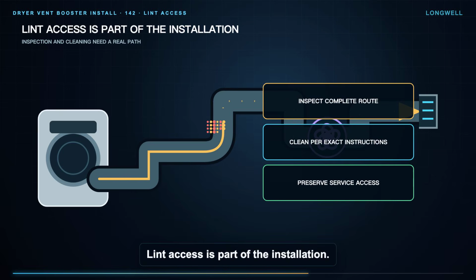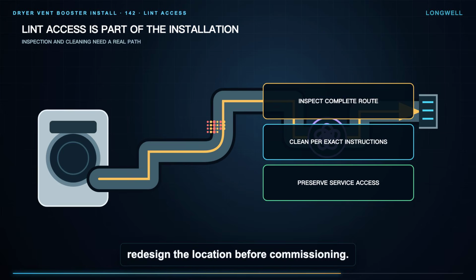Lint access is part of the installation. The fan, sensing method, and surrounding duct cannot be allowed to turn a hidden restriction into a harder maintenance problem. Before closing the work, confirm how the complete route will be inspected and cleaned, what access the exact product requires, and what condition calls for service. Maintenance timing is not universal, so use the dryer and ventilator instructions and observe lint loading. If access cannot be preserved, redesign the location before commissioning.